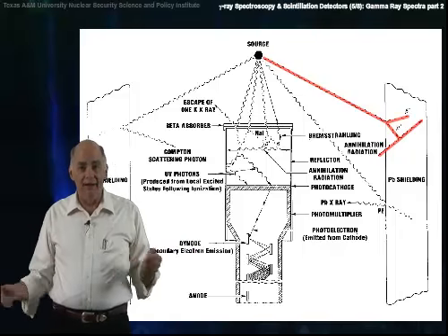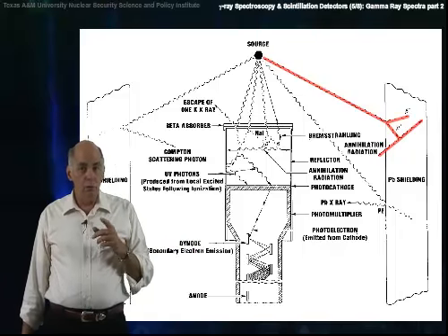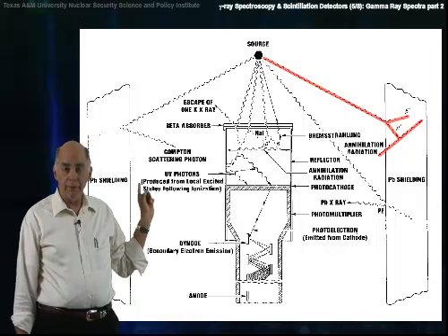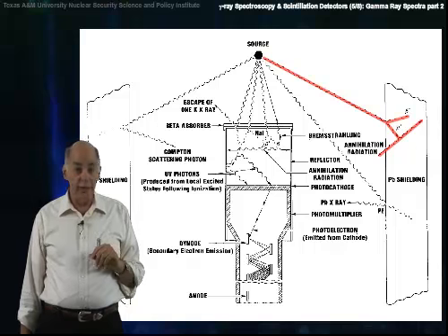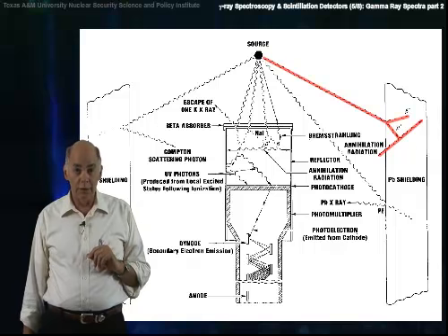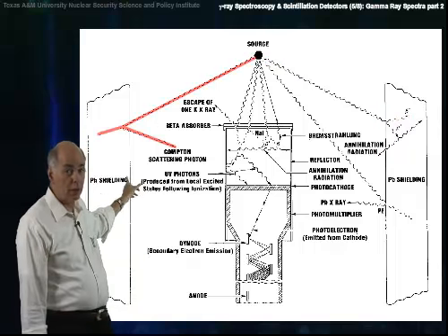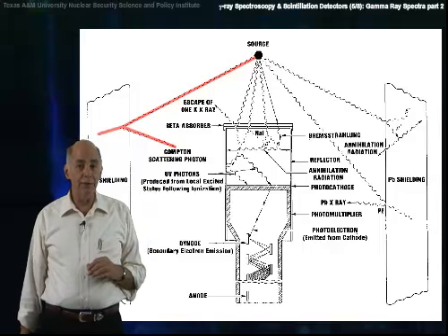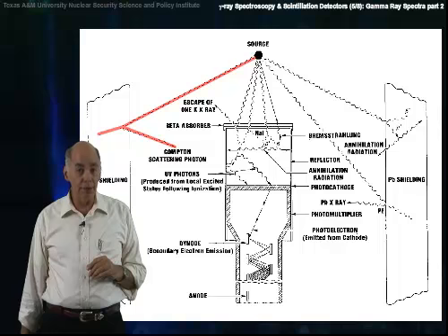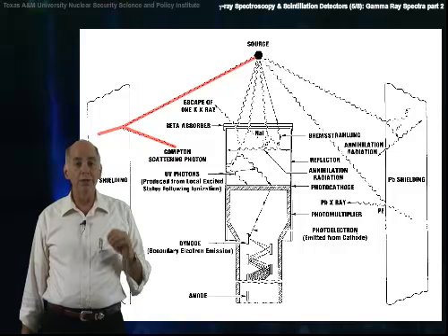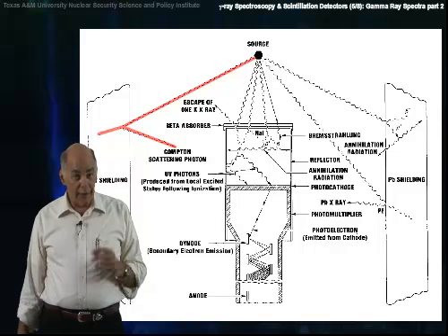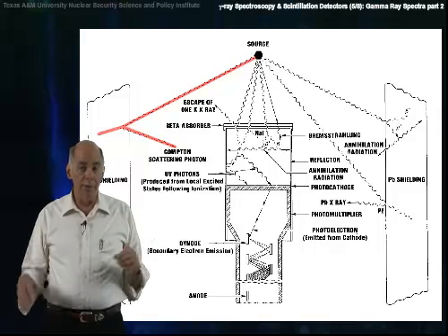Well, so what? Well, we're trying to measure the radiation coming from the source, and this 511 photon is not from the source. As shown here, a gamma from the source can suffer a Compton interaction in the shielding, and the resulting Compton photon can be counted. And as before, this is not part of the original spectrum.